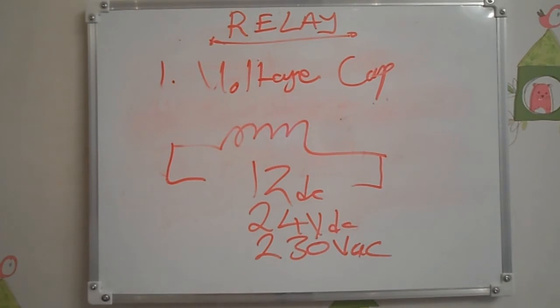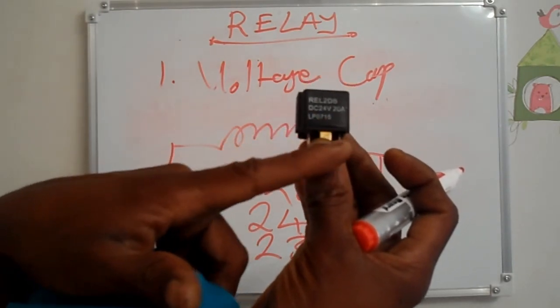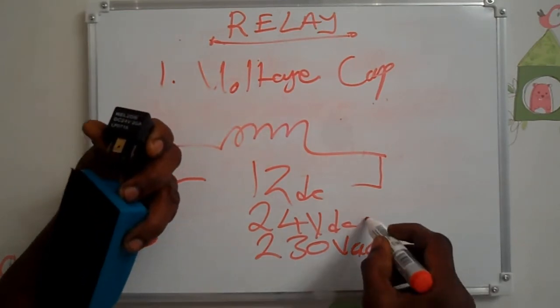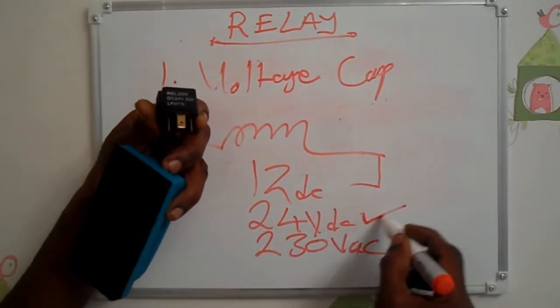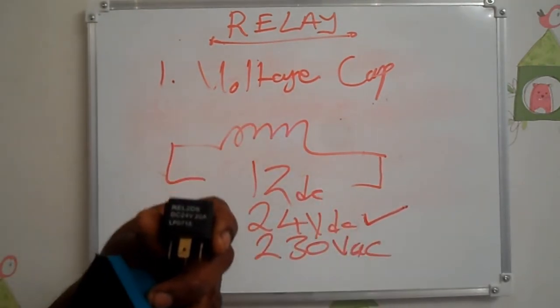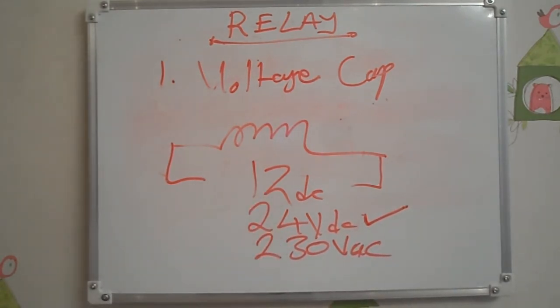In DC voltage you have 12 volts DC and 24 volts DC, so it depends on the area of your application. For example, look at this relay — you see DC 24 volts, 20 amps. So this relay I'm holding: if you give it 12 volts you cannot trigger it, and if you give it 230 volts AC it will burn the coil. That is the voltage classification by voltage capacity.